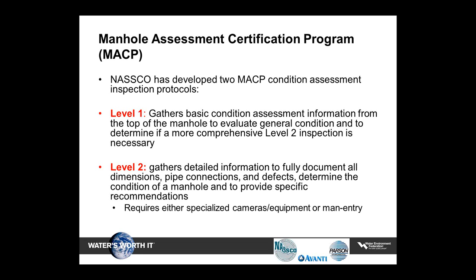With Level 1, we're trying to gather basic information from the top of the manhole — not entering the manhole — to get some basic information, including whether a Level 2 inspection is necessary. The Level 2 type of inspection allows us to gather more detailed information to fully document the dimensions, pipe connections, and defects within the manhole to make intelligent decisions on whether and what type of improvements or rehabilitation is necessary. Level 2 does require either specialized cameras and equipment or man entry.